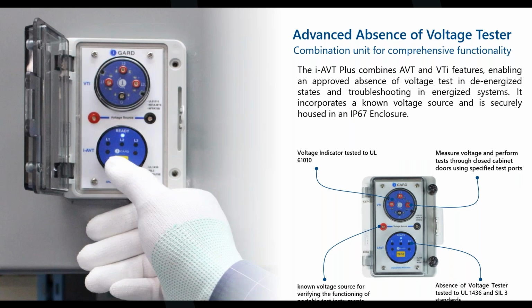The i-AVT Plus is a next-generation safety device that combines the function of an approved absence of voltage tester and the voltage indicator in one unit. It ensures compliance with UL 1436 and SIL3 standards by providing a reliable way to confirm that equipment is truly de-energized before the work begins. Unlike simple indicators, the i-AVT Plus performs an actual absence of voltage test at the point of work and includes a known voltage source for verifying portable testers. It also allows safe troubleshooting through closed-door test points, all housed in one IP67 enclosure for maximum protection. This combination delivers unmatched safety, accuracy, and convenience for electrical maintenance.